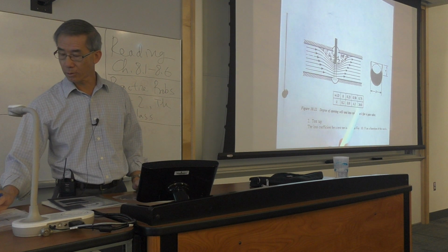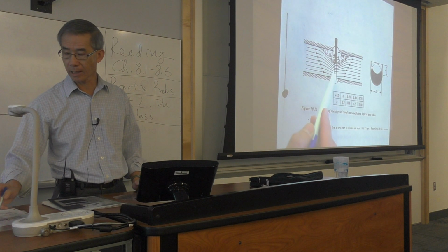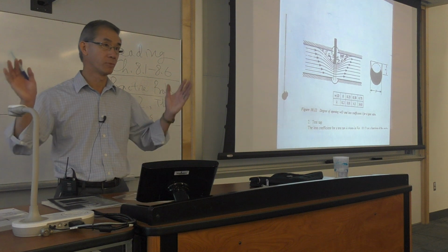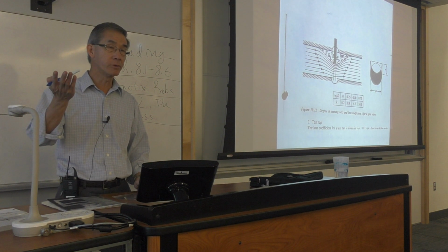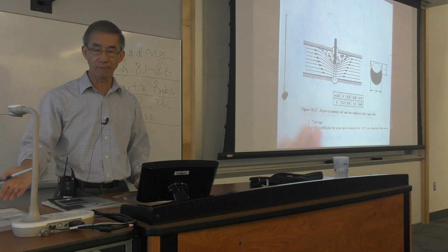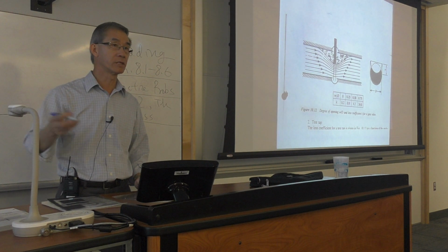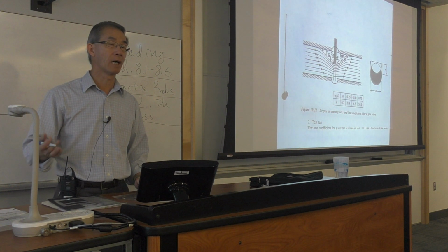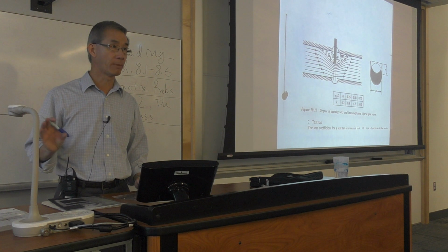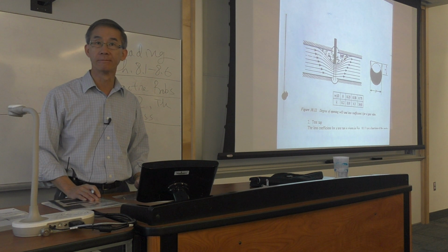When it's 3/4 closed, very much down, you have losses that are way higher, 20 plus. So as an engineer, if you are the customer who buys the valve and designs the flow system, you can use this chart to determine how much pumping power you need for different flow rates throughout the power plant, because it's not always constant.